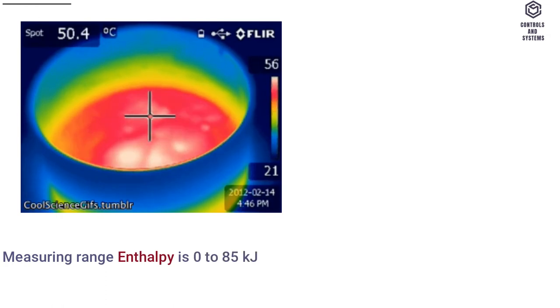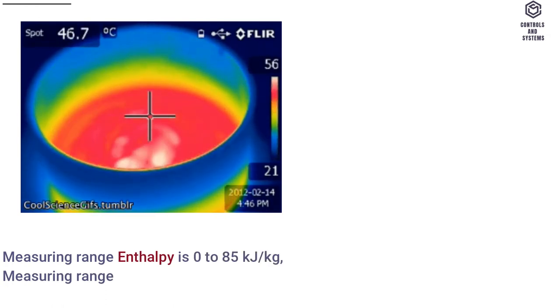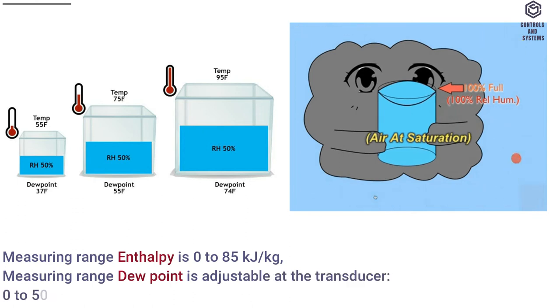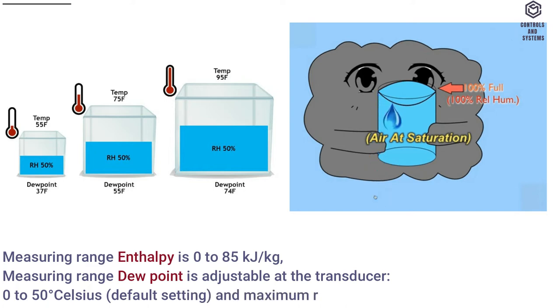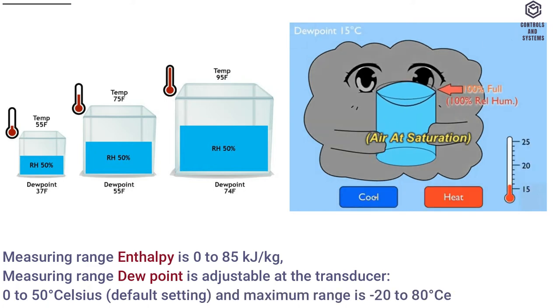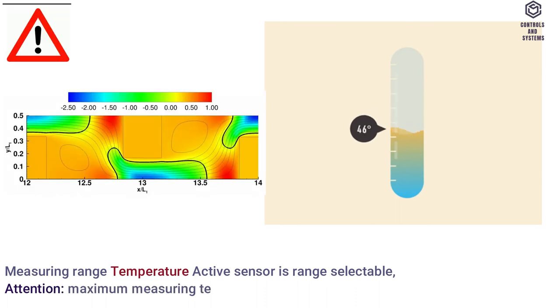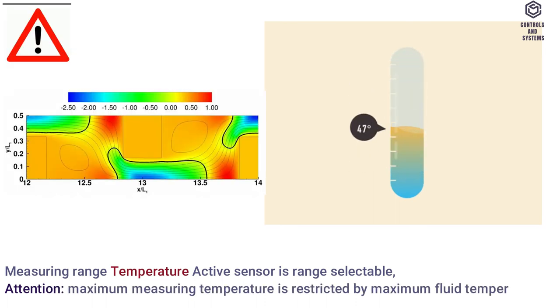Measuring range enthalpy is 0 to 85 kJ/kg. Measuring range dew point is adjustable at the transducer: 0 to 50°C default setting, and maximum range is −20 to 80°C. Measuring range temperature active sensor is range selectable — note: maximum measuring temperature is restricted by maximum fluid temperature.